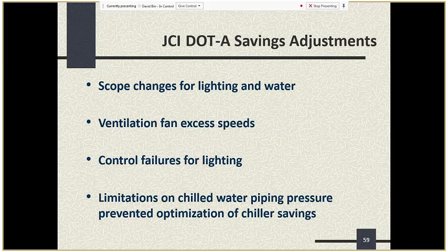And I already talked about the top two of these, anticipating what I was going to say. One we didn't mention is that the dedicated control system for lighting had some issues in a few locations, and because of that, JCI was not able to count savings because, being unable to control the lighting to deliver the desired schedule for illumination, they actually, I think if I recall right, Larry, they just overrode the controls because they weren't working properly, and they had to forfeit the savings, at least temporarily, until they could get those lighting controls back under control. Is that accurate? Yes, that is. Yeah.